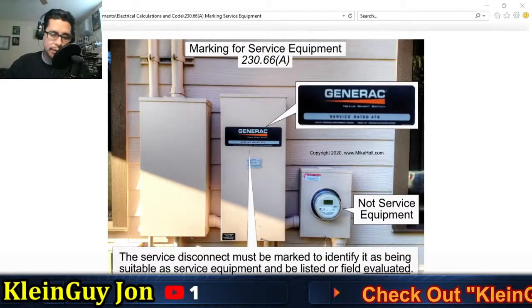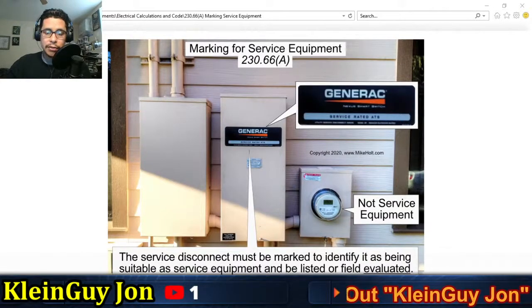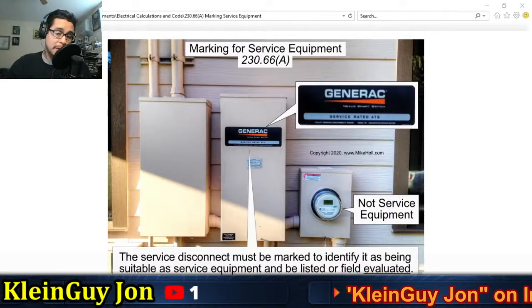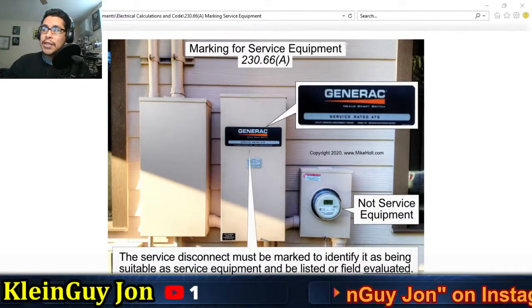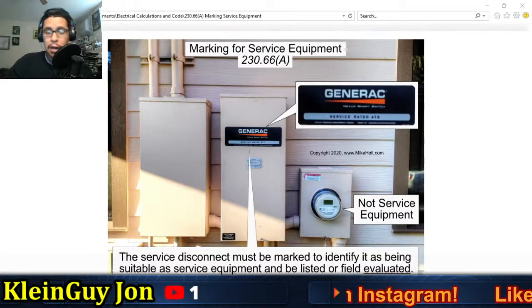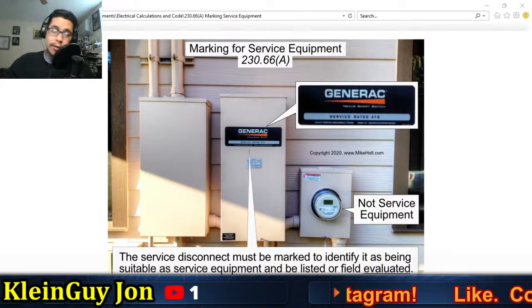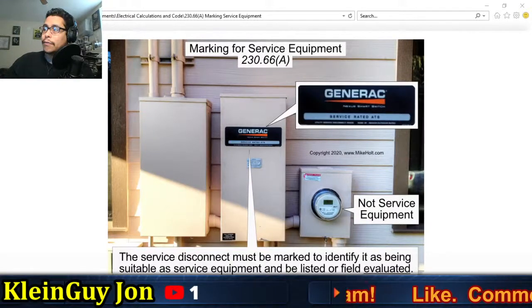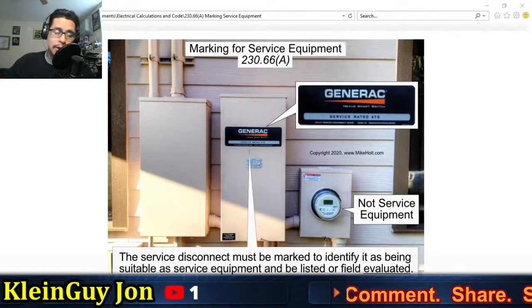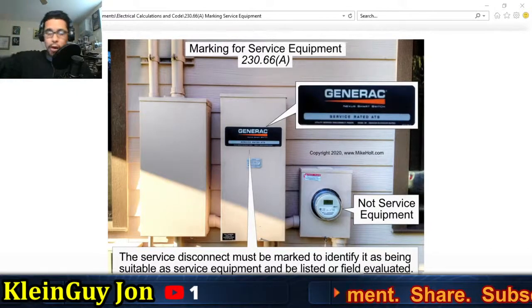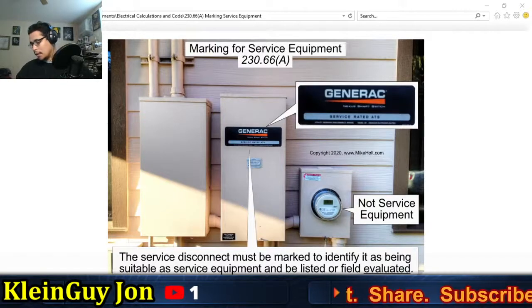Remember, the meter is not service equipment unless it's a combination main service, in which case it has to be considered a service. But if it's not part of the disconnect, not inside the same enclosure as a combination—I like to call those combos—then this will be listed as not service equipment, while these two will be marked, not listed, but marked. That's what I meant to say.